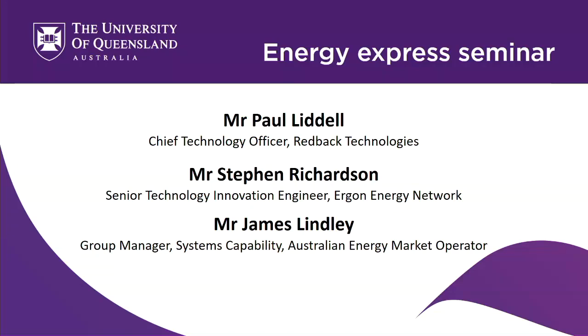So the question for people who can't hear was: are we doing testing to make sure the inverters stay online when there's, say, a harmonic or voltage disturbance on the line while we're potentially providing network support? The answer is there are standards we comply with, but I think it's an area where industry needs to get together with manufacturers as well. It's very difficult for us to test those scenarios with our equipment because you need a virtual network. Some of the university equipment enables testing those scenarios, and it's something we'd like to get into more.